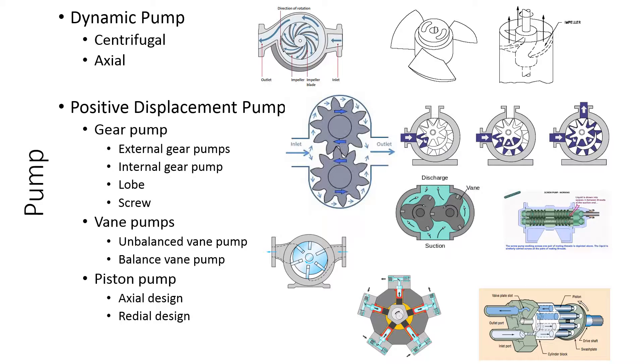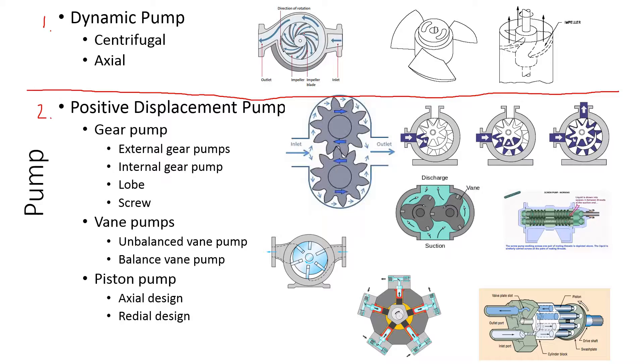Pumps can be divided into two main categories: dynamic pumps and positive displacement pumps. Dynamic pumps work primarily on pressure difference. Looking at the impeller, when it rotates, a vacuum is created right behind the impeller blades. Rotating quickly creates a vacuum inside the housing, while the outside, for example, is at atmospheric pressure.